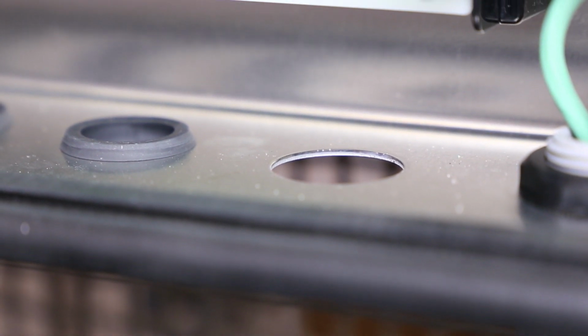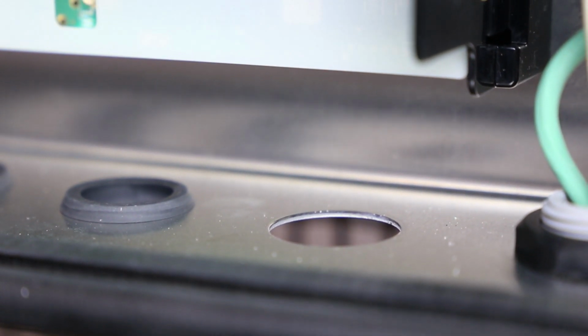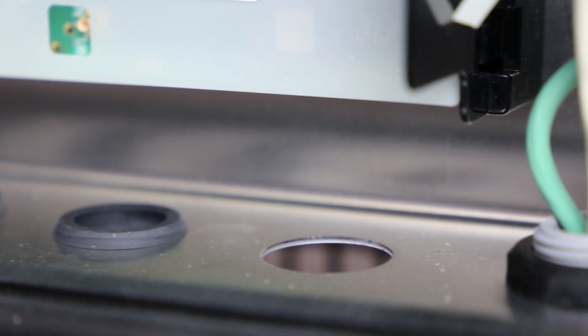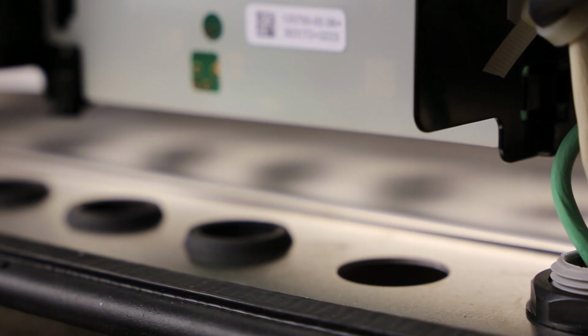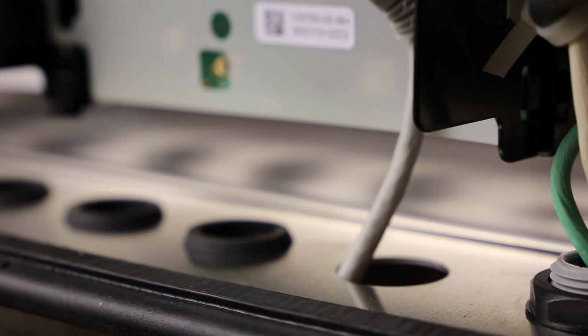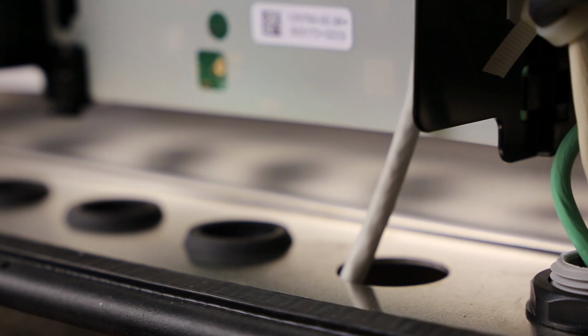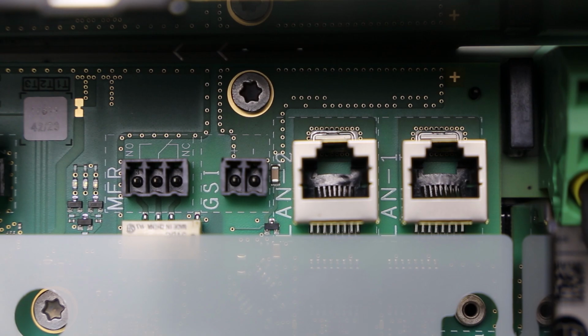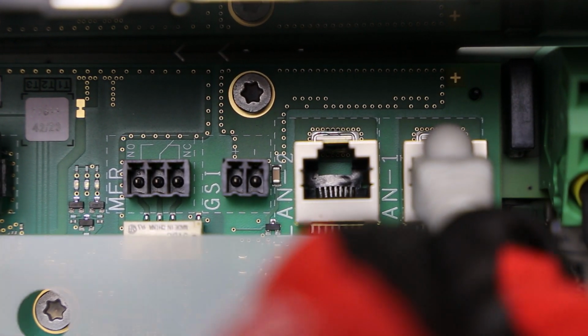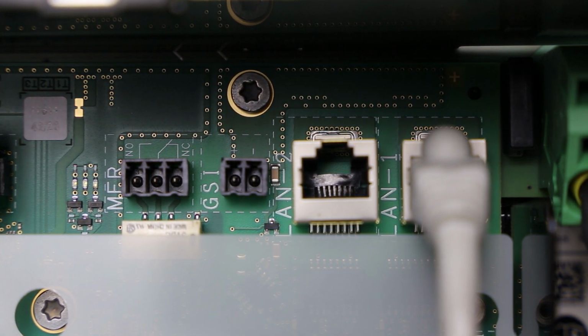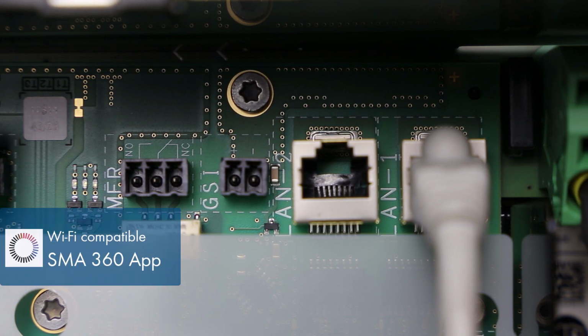To safely handle communication wiring, first remove a second knockout plug and then run an Ethernet cable from the homeowner's router and through the knockout. Using a second knockout will help avoid any contact between the AC and communication wires. Plug the Ethernet cable into any one of these ports. The other unused port can be used for the SMA energy meter. Or you could connect to the homeowner's Wi-Fi network via the 360 app.